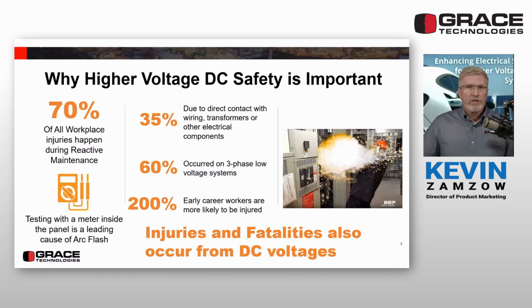While the percentages and numbers you see on the screen may vary depending on the source, OSHA remains the best source for reported incidents. Testing for the absence of voltage inside of a panel is unfortunately a leading cause of arc flash and electrical injury. With the retirement of many qualified electricians and high turnover at maintenance services companies, there are more early career and less qualified workers performing lockout tagout. Adherence to electrical safety programs may not be as high as needed to keep workers safe.